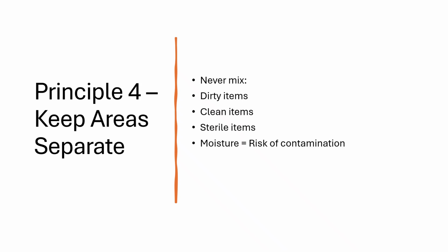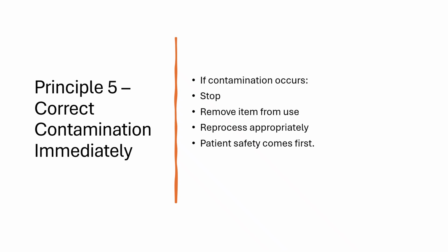Dirty, clean, and sterile items must always remain separated. Contact between these areas compromises the integrity of the process. Moisture is especially dangerous because it allows microorganisms to pass through packaging materials. When contamination occurs or is suspected, immediate corrective action is required. No item should be used if there is uncertainty regarding its cleanliness or sterility. Protecting the patient is always the highest priority.